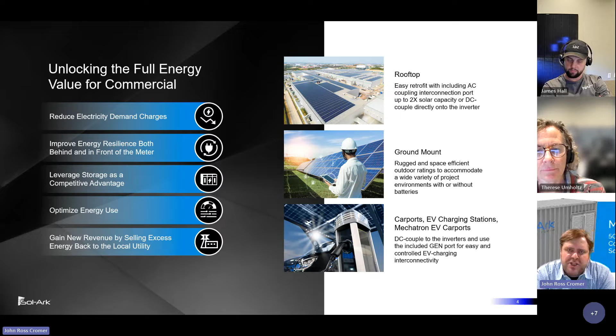The Sol-ark inverters do a seamless transfer, whereas some larger containerized storage solutions have a transfer time of as much as 1 minute. But because we use these more modular string inverters, we can do a much faster transfer time. So it's seamless transfer for commercial application. Scalable architecture: this system works for 1 inverter and 1 battery cabinet. It also works for 12 inverters and, indoors, up to 16 battery cabinets per inverter. So you can do 11.5 megawatt hour battery banks with this architecture, as well as 60 kilowatt hour battery banks. So incredibly scalable.